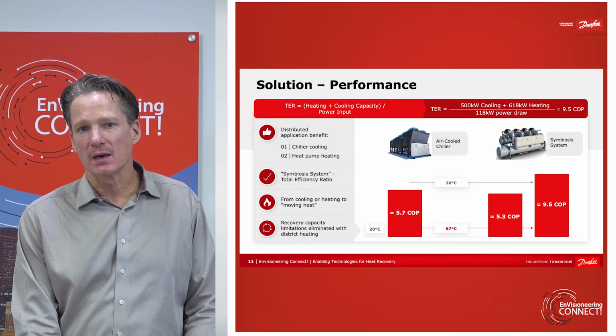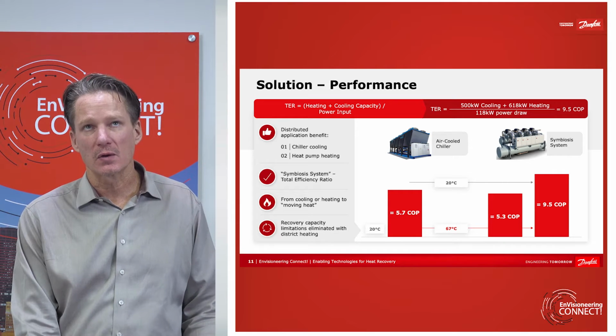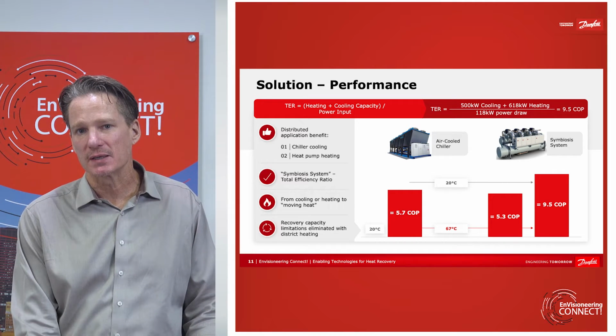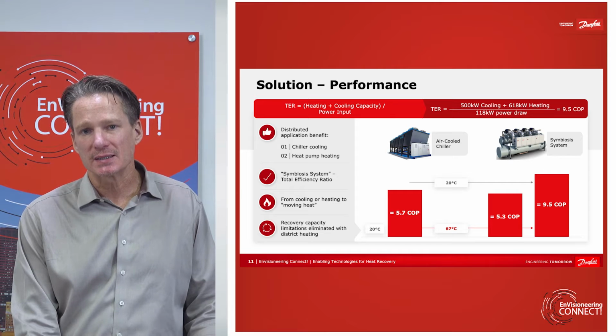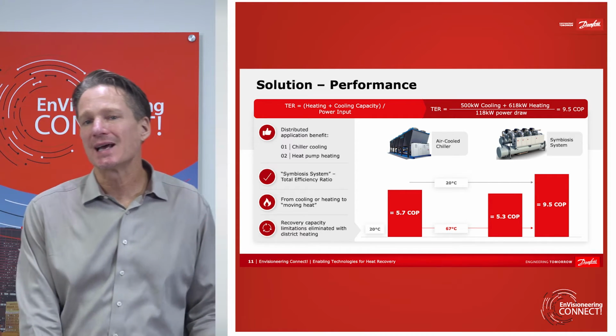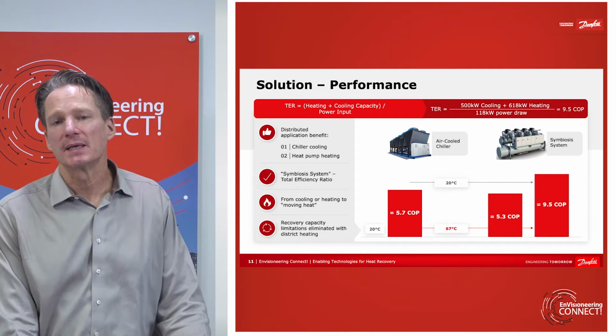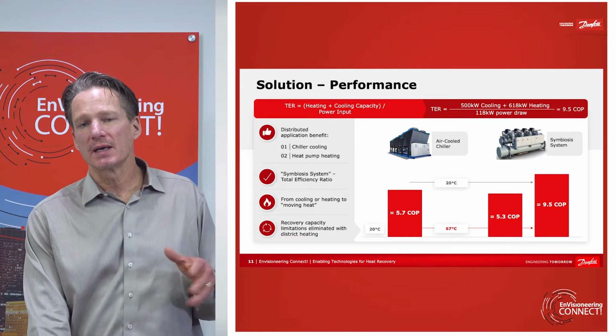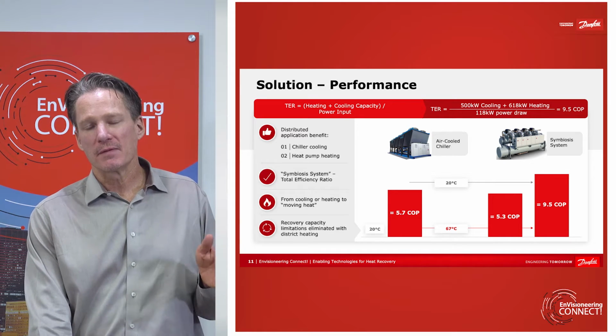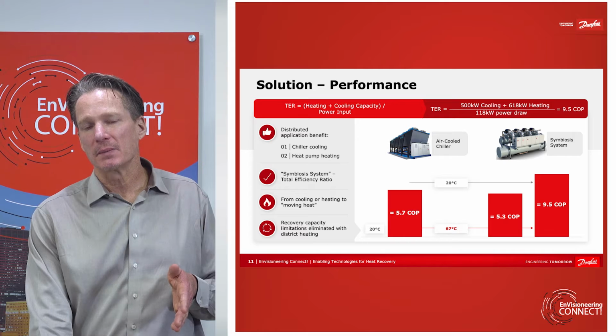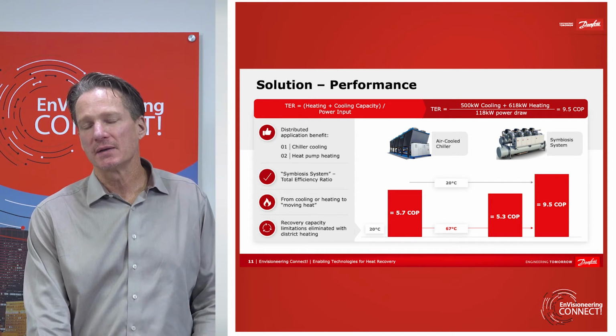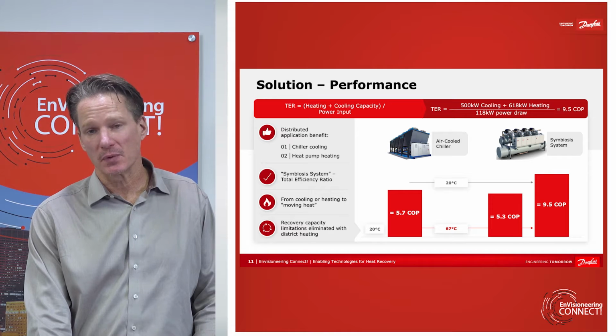So again, shown here are air-cooled chillers that were originally providing the 20 degrees C to the data center, operating on a design day at about a 5.7 COP. As we integrate in the water-to-water heat pump, if it was only providing that heating, it would be at about a 5.3 COP. But the combined cooling and heating efficiency, or symbiosis, is about 9.5.